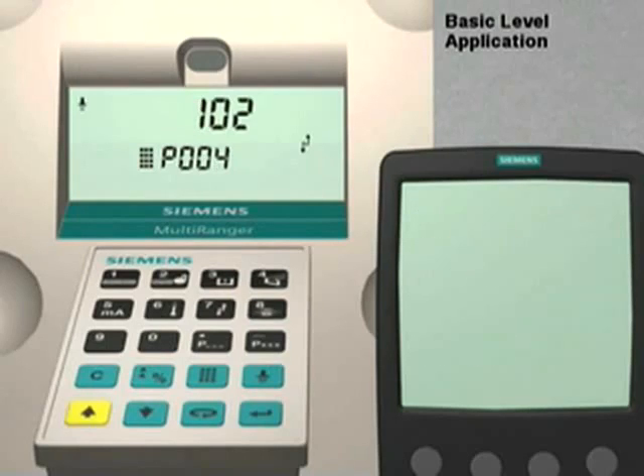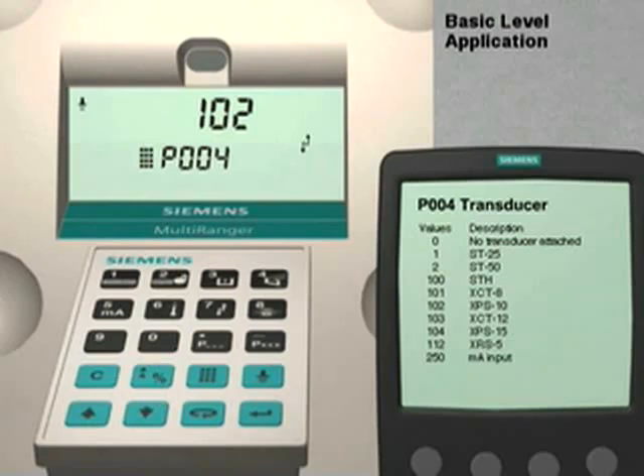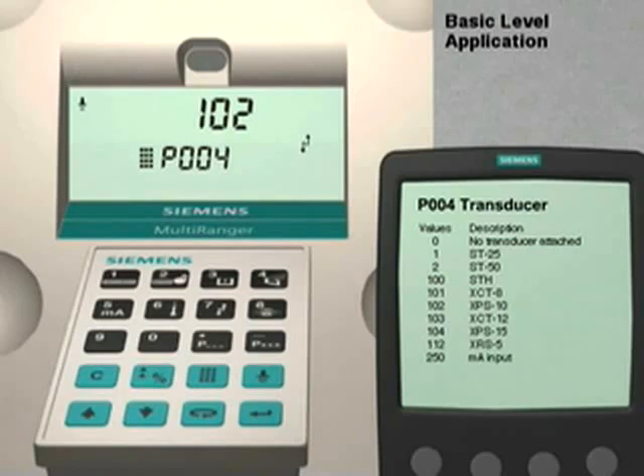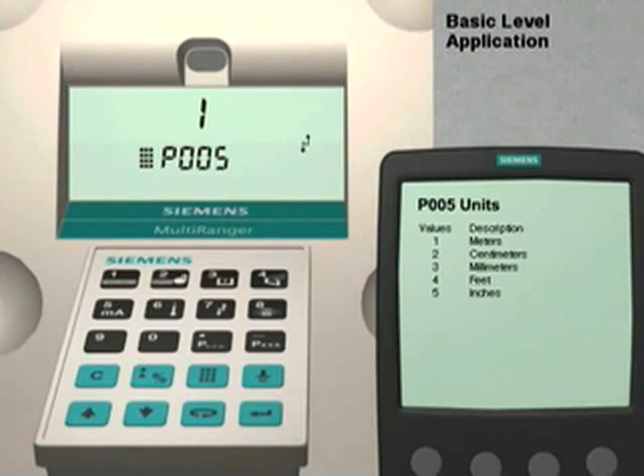Use the up arrow key to go to parameter number 4. Parameter 4 optimizes the multi-ranger for the specified input. The input can be either a transducer or a milliamp input source. In our application, we are going to use an Echomax XRS 5 transducer. The XRS 5 transducer has a numeric value of 112. We enter 112 and then the Enter key to set this value. Press the up arrow key to go to the next parameter.